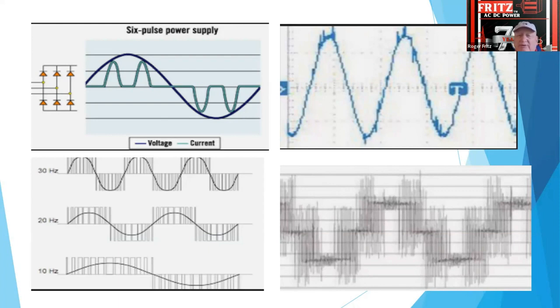So that's why it's important that engineering always designs motors to be oversized, because they don't want to run into a situation. And the pump is oversized, as it has a wear factor, they want to always be able. A rule of thumb used to be about 125%. So most motors are running faster than they need to still accomplish their flow requirements, and then they do it with valves and those things to cut it back. So the key is to get that understanding, and I don't want people hung up on this being really complicated. Literally all we're doing is building a variable power supply that we can use to speed up and slow down the motor.